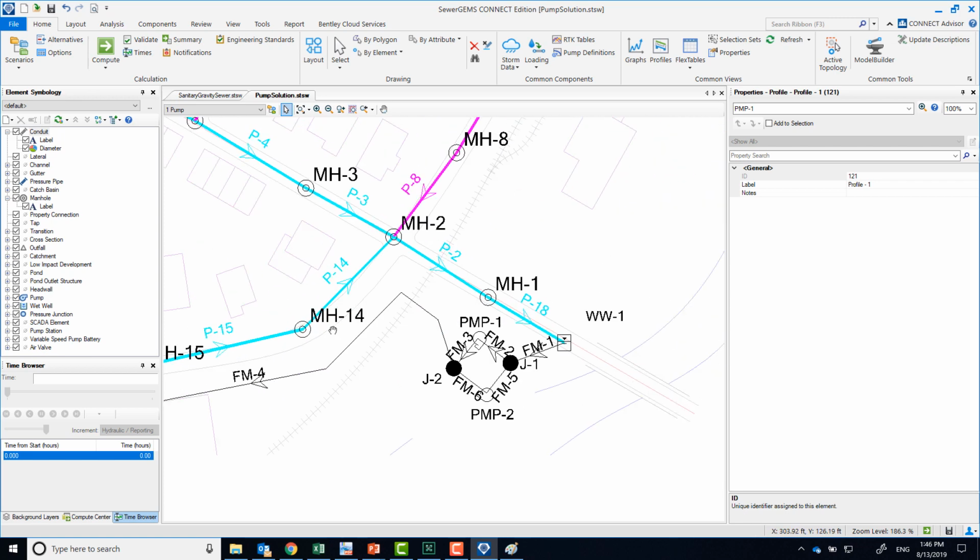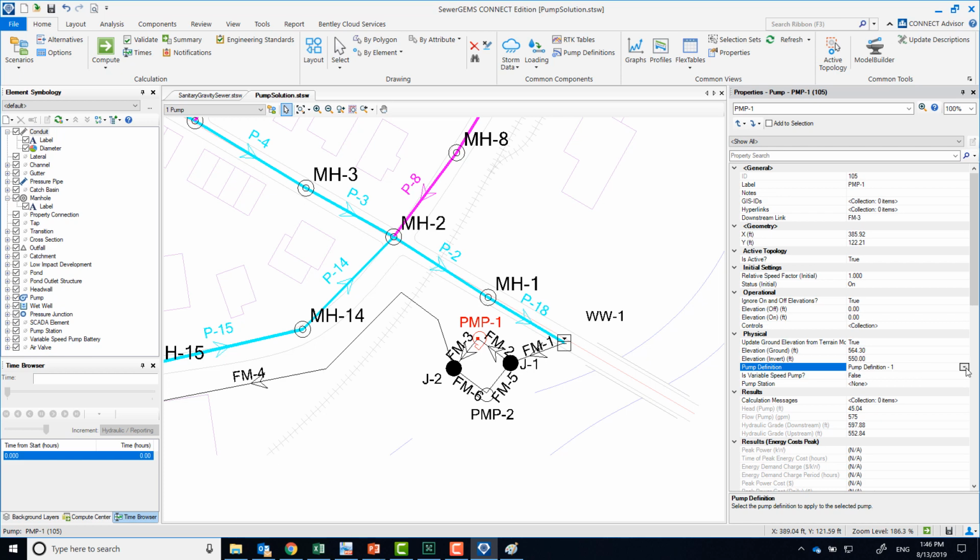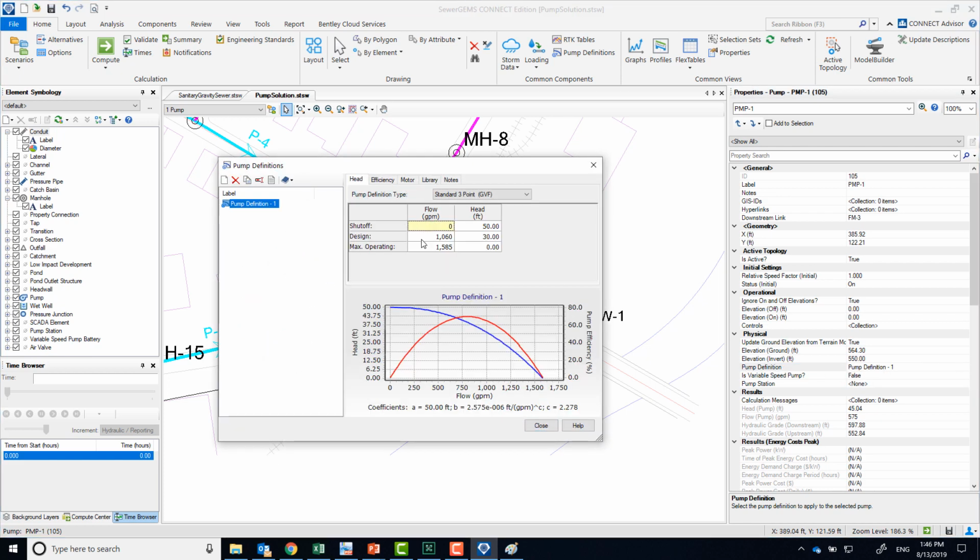So, now that we have that in mind, let's go back and look at our pump definition. This pump is meant for a design point of 30 feet. So right there, instead of being where it should be, about 1,000 gallons per minute and 30 feet, which is right here, if you can see my cursor, now it's basically operating right about here.